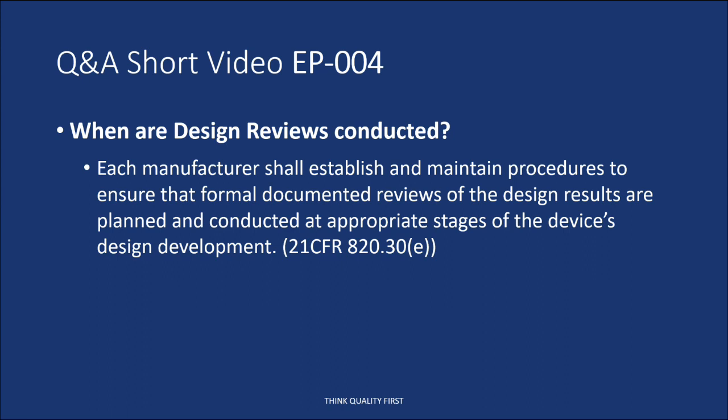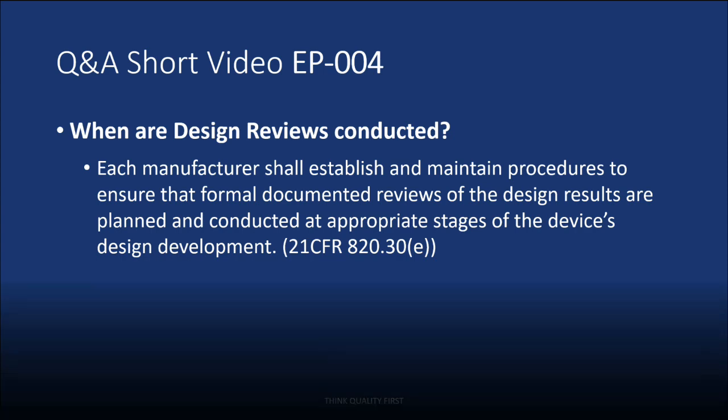The company SME will interpret the requirements from the regulations and establish a design and development process to meet the complexity of their product. The resulting SOP will include the requirements for formal design reviews as determined by the company's SMEs. Examples of design review phases are design input, design output, design verification, design validation, clinical design reviews, design transfer, etc. Keep in mind there are the formal design reviews and there are other reviews.